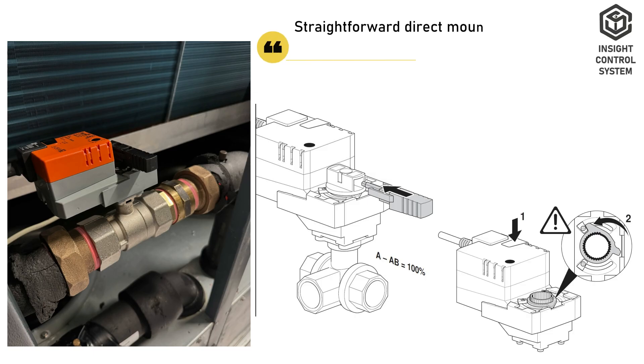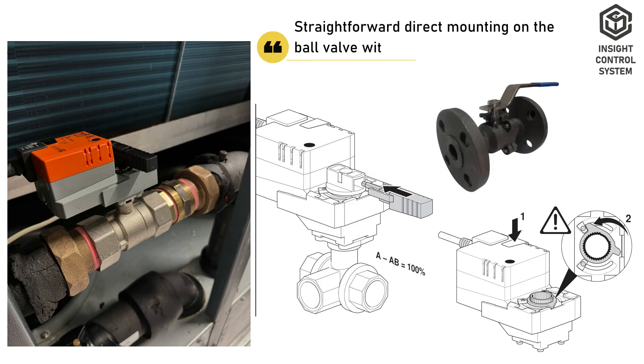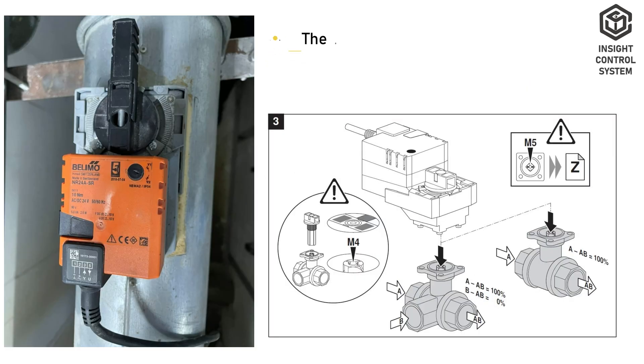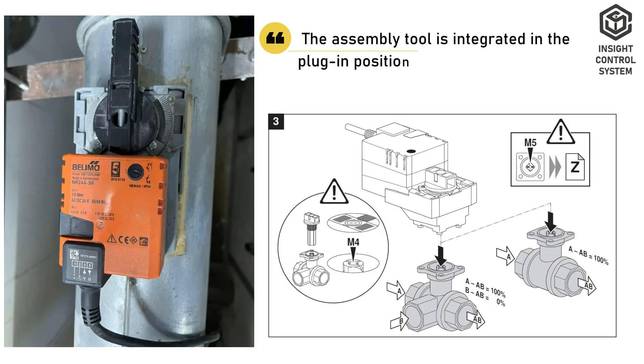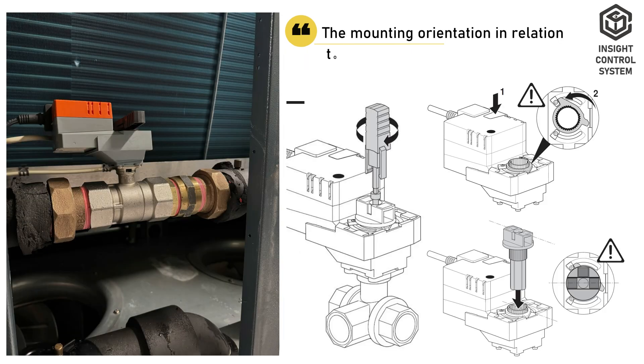Mounting: straightforward direct mounting on the ball valve with only one central screw. The assembly tool is integrated in the plug-in position indication. The mounting orientation in relation to the ball valve can be selected in 90-degree steps.